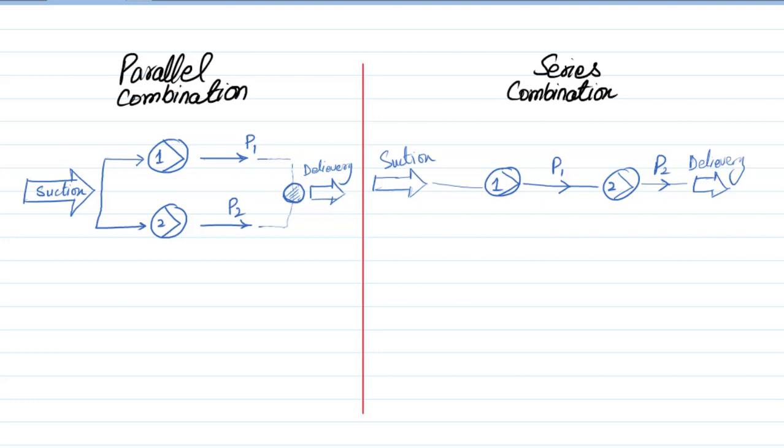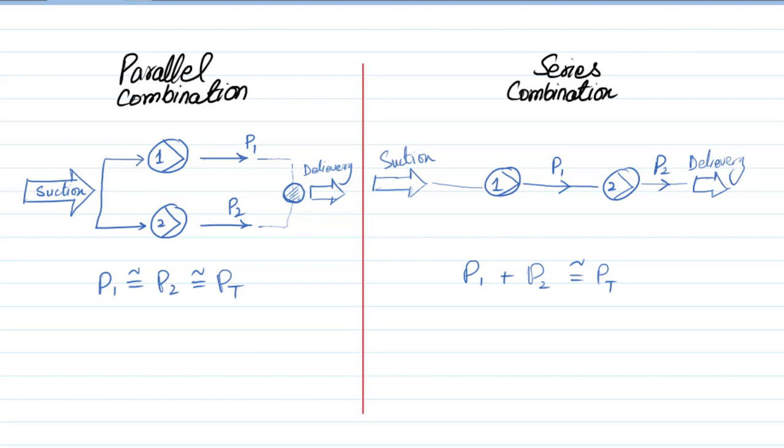Note this important point for parallel combination: both pumps should be identical. If pumps are identical, obviously they will create same pressure. So P1 pressure equals P2 which equals total pressure at delivery point. In real case this is not equal actually because of friction losses. And in series case, one pump's pressure adds to the other pump's pressure and the delivery point pressure is the sum of both.